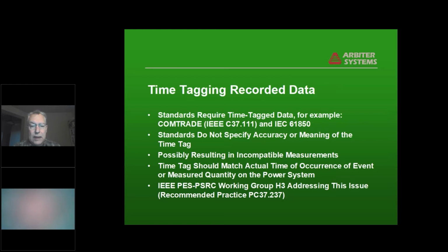A number of standards require time tagging data. You're probably familiar with IEEE 61850 and ComTrade. They provide fields for putting the time tags in the data stream, but most of them don't specify accuracy or even what time scale you're using. And that can result in measurements coming from different places that are incompatible. It's important that the time tags that are recorded have to match when something actually happened.